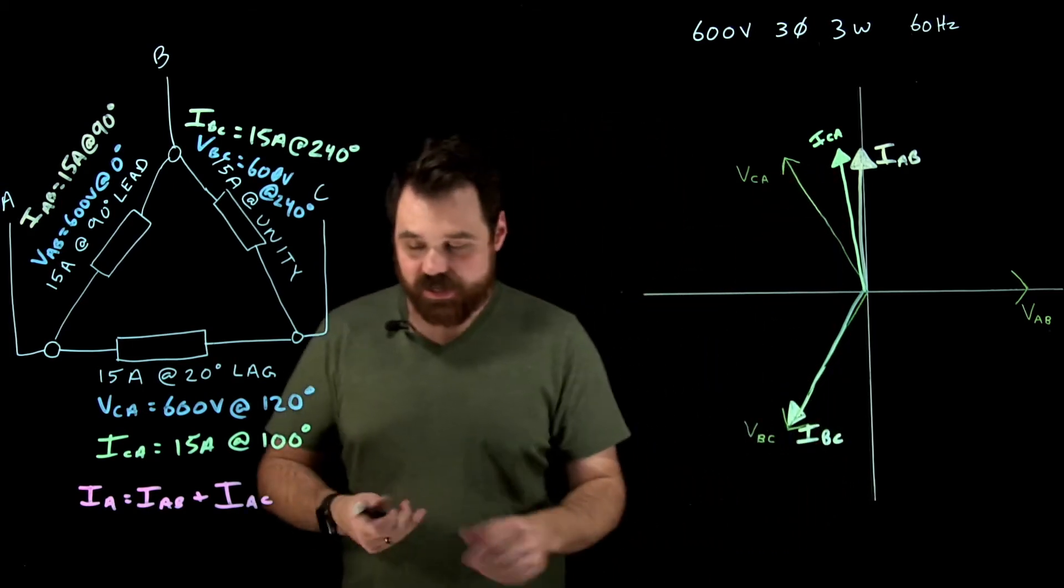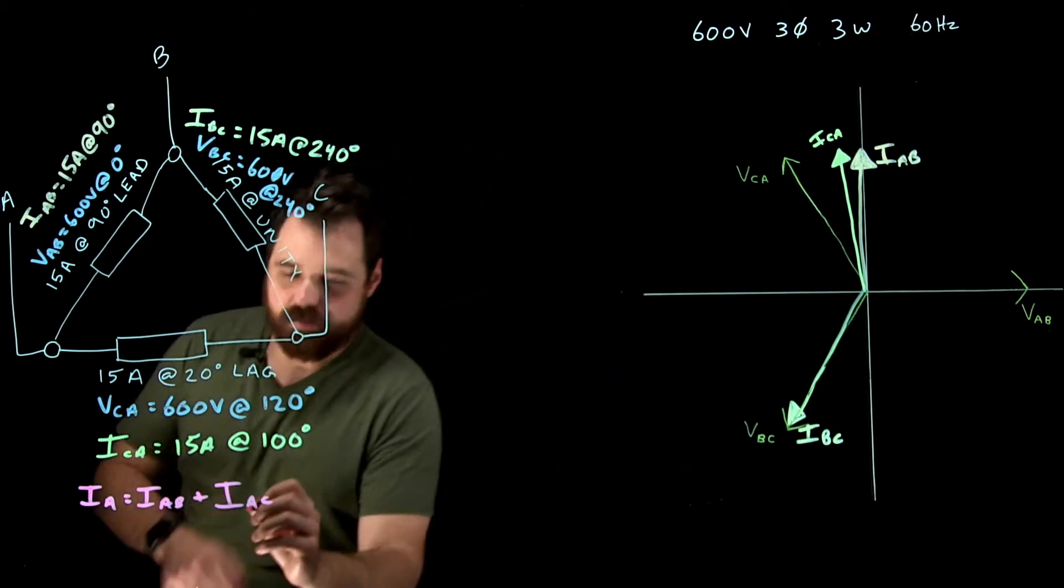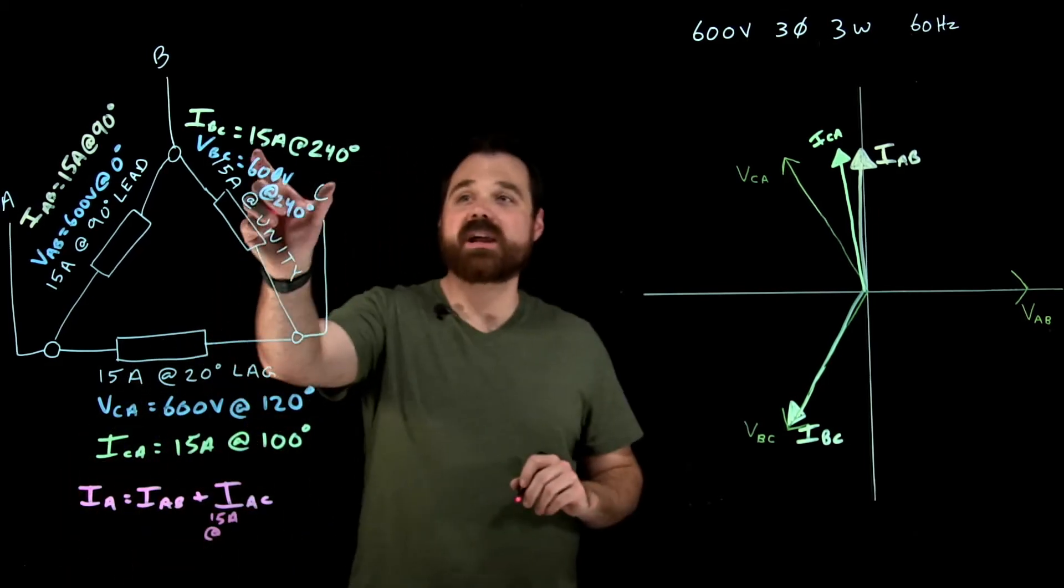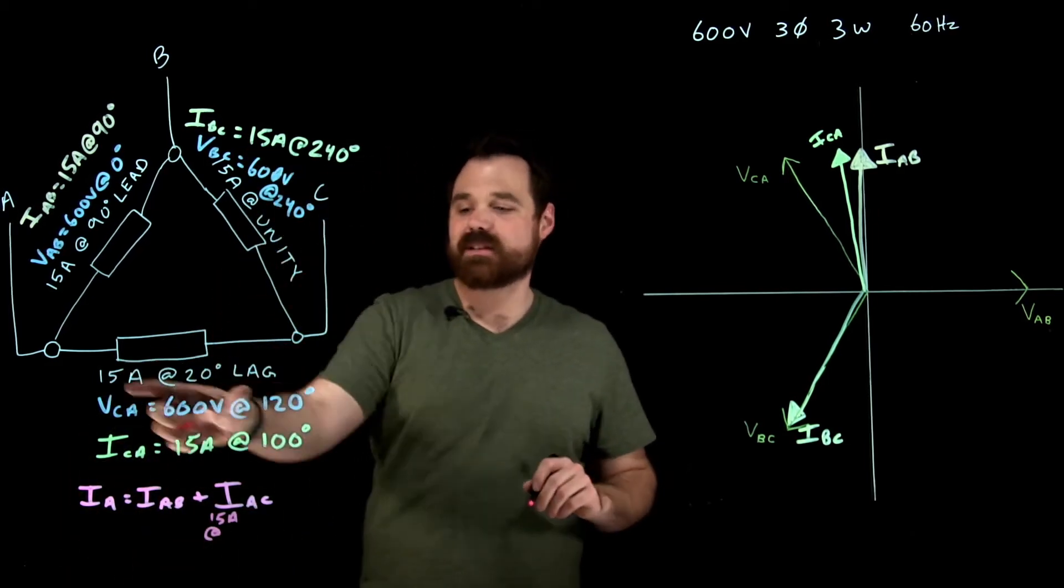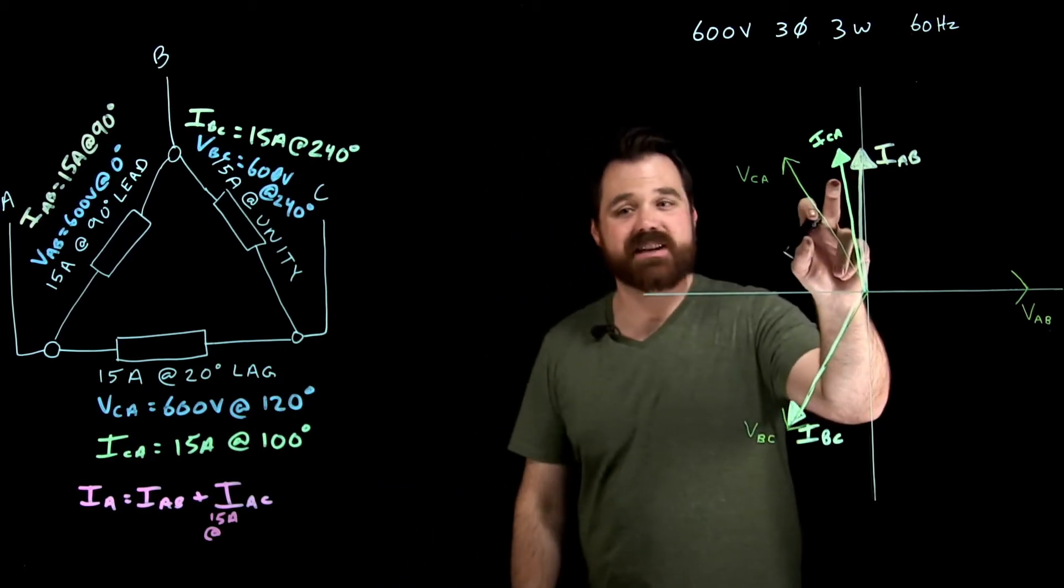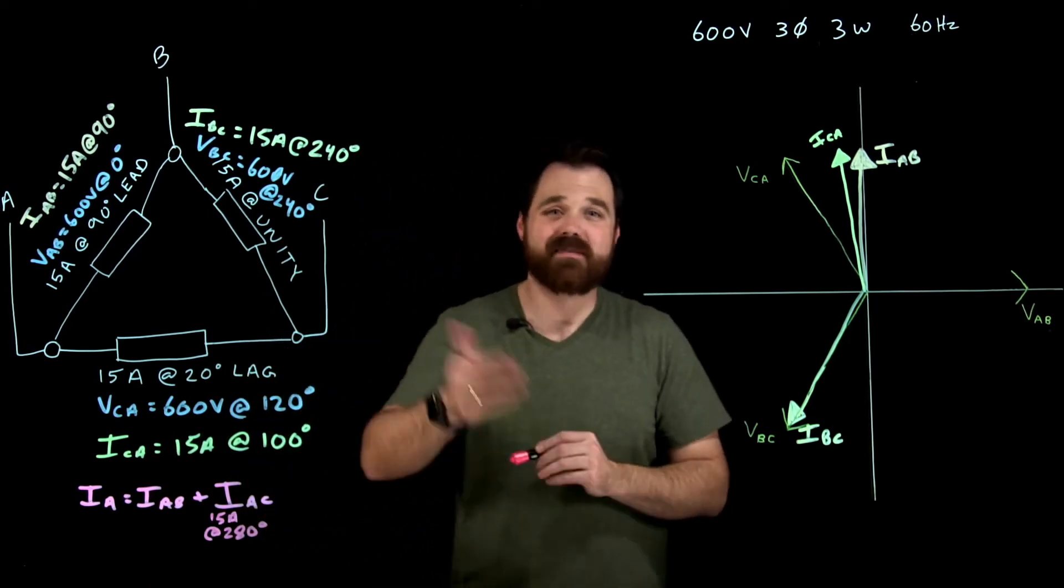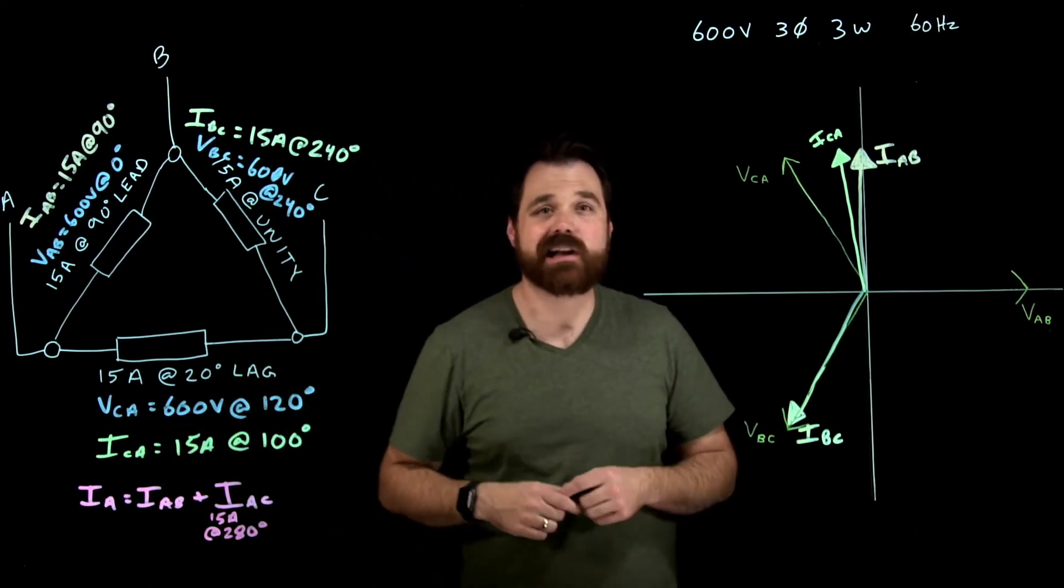So I A to C is actually going to be right here. I'll write it down right here 15 amps at 280 degrees from C to A. So C to A is at 100. So this one is going to be at 280 degrees. So it's the direct inverse of that. So that's how we would calculate I A.